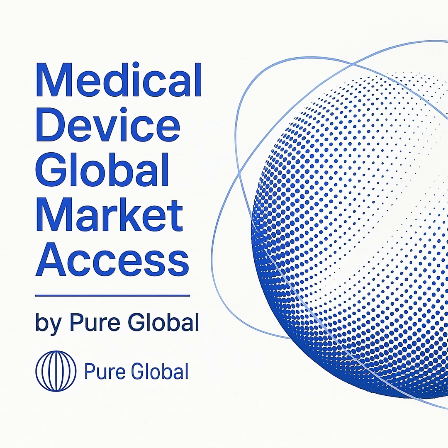While your existing data is valuable, gaps must be addressed. Your Quality Management System, or QMS, certified under ISO 13485 for Europe, must also comply with the FDA's Quality System Regulation, found in 21 CFR Part 820. While the FDA is working to harmonize its regulation with ISO 13485 through the new Quality Management System Regulation, or QMSR, compliance with 21 CFR 820 remains the requirement today.